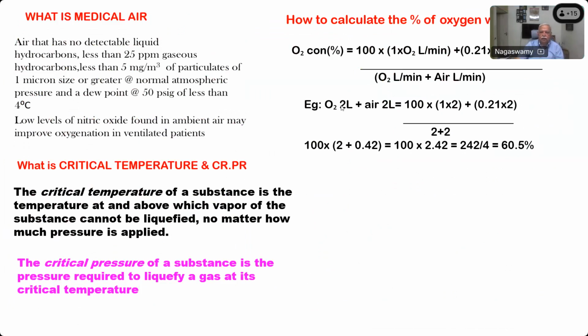You can calculate it according to what you are using, whether 1 liter or 2 liters or 250 liters, whichever ratio you are using. If you are using less oxygen and more air, will the percentage come down or will it go up? Because you have to take into consideration the total volume you are delivering also. Okay, so it will come down if you are using more air and less oxygen.